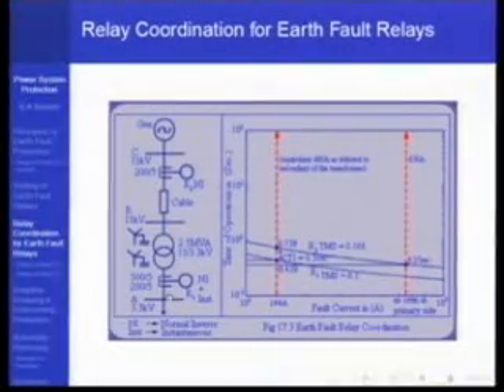Okay, this is another example system which is worked out. We'll quickly have a look at it. Star grounded transformer, another cable, then another 11 kV system and a source, and we are trying to coordinate the earth faults of these two. Here there is a normal inverse plus an instantaneous characteristic available, and here you have only a normal inverse characteristic. The CT ratios are 500:5 and 200:5. I'm not very sure which one, but 500:5 probably for the instantaneous and 200:5 for normal inverse. And this one is 200:5 here, because the fault current seen here will tend to reduce anyway.